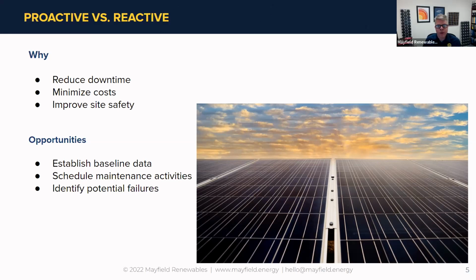One thing I'll mention over and over: I'd recommend grabbing a copy of the IEC 62446 standard, which covers commissioning and O&M. There are two or three parts to that spec, and it's referenced repeatedly in specs from system owners. If you don't have it, put it on your wish list of documents, because it will help identify these tests, what the thresholds are, and what the baseline data needs to be.